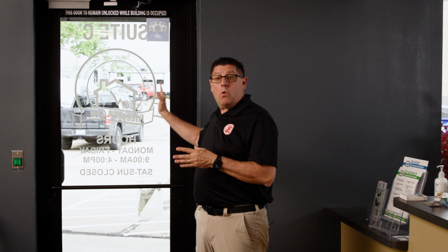Within the life safety portion of the inspection, you're going to be called upon to look at exit doors. When looking at exit doors, first and foremost, every exit door in the property should open outward, in the path of your exit. It must be at least 32 inches wide and open 90 degrees or more as you're leaving the building.